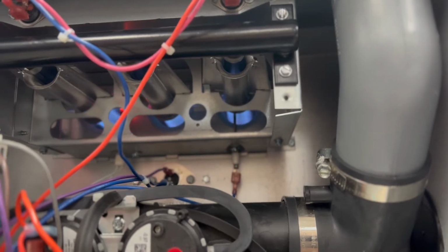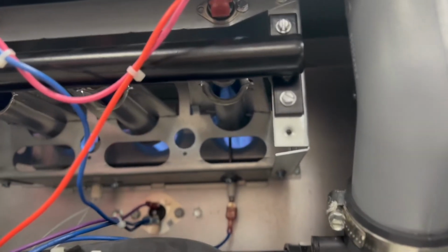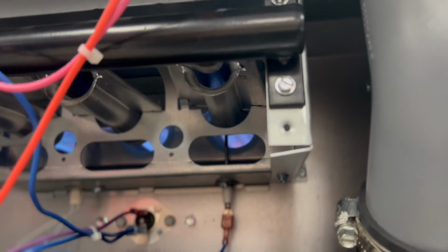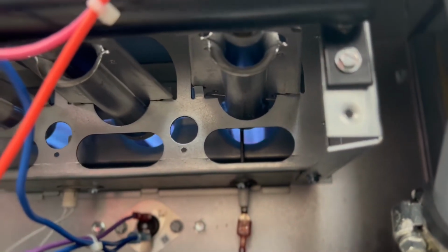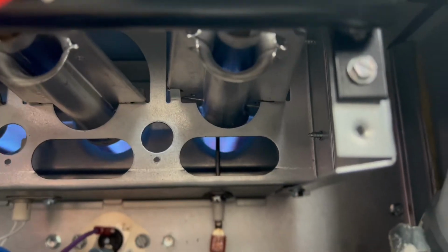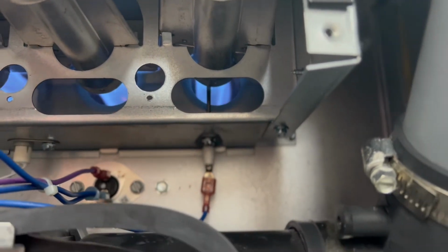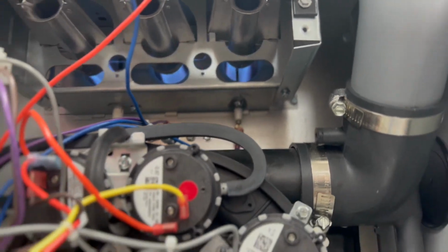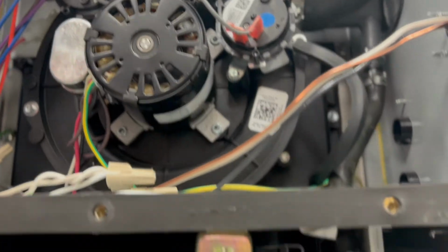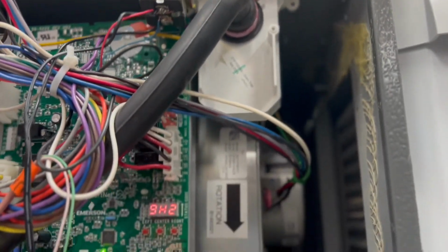After it lights all the way across, on the far side of it, there is a flame sensor. This is used to prove the fact that we have flame in the furnace. It will then send a microamp signal back down to the circuit board saying, yes, we have flame, keep going with your process towards heating the home.